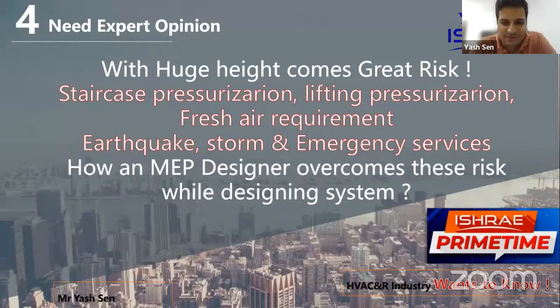This is a big problem because sometimes the sensor won't work after 1 or 2 years, or sometimes the VFD is not working. So we have to regularize maintenance of the system so that at the time of a fire event, we can use it beneficially. In the staircase and lift well, we do the same thing. For big buildings, we divide 4 or 5 floors by one fan, or use an axial fan with VFD controlled by a sensor inside the space, along with an automatic damper. Sometimes this damper doesn't work, and sometimes there's a pressure problem inside the well. These are the challenges we need to rectify to design the perfect system.